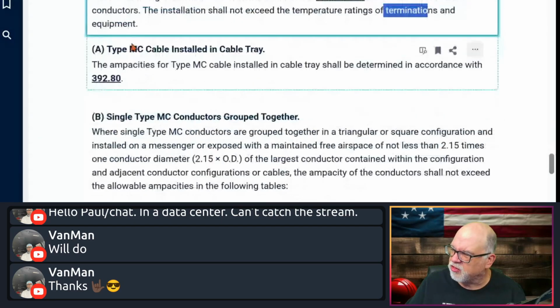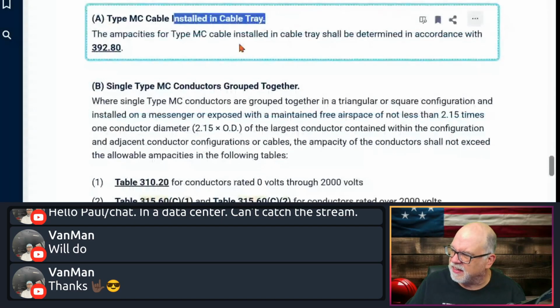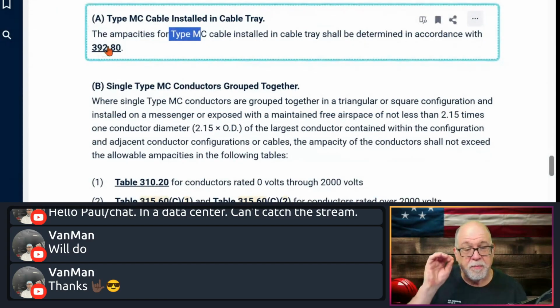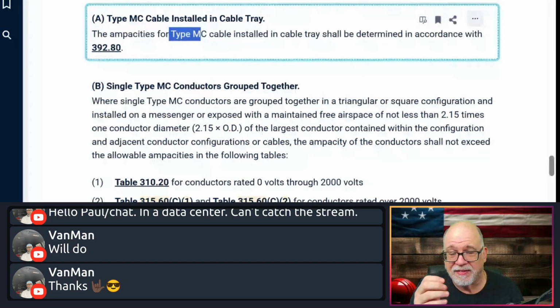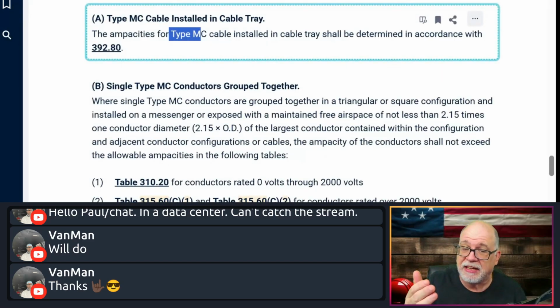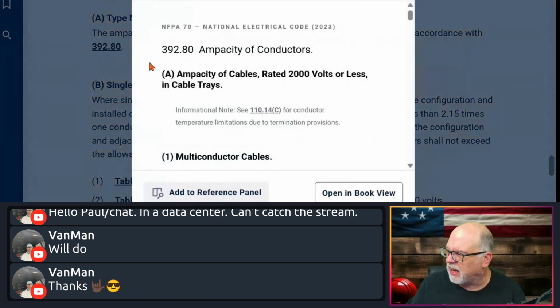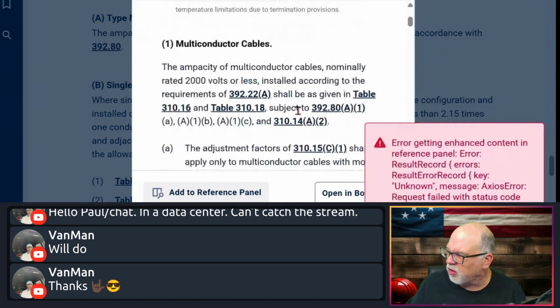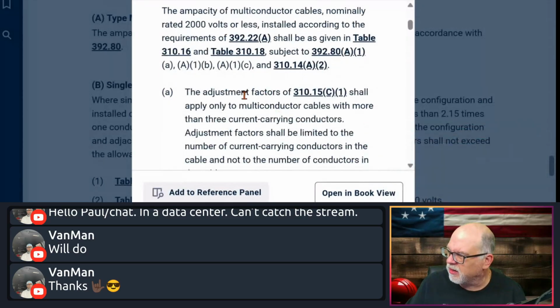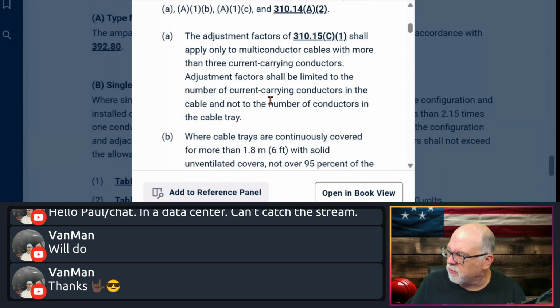A, it says MC cable installed in a cable tray. It says the ampacities for MC cable installed in a cable tray shall be determined in accordance with 392.80. Important to remember, we have normal ampacity situations, but if you're going to install this MC cable in a cable tray, which you can do, 392.10 permits this, it is a cable assembly, then you have to follow some rules up here. And if you look at 392.80, you'll see that it talks about some of these rules down here.